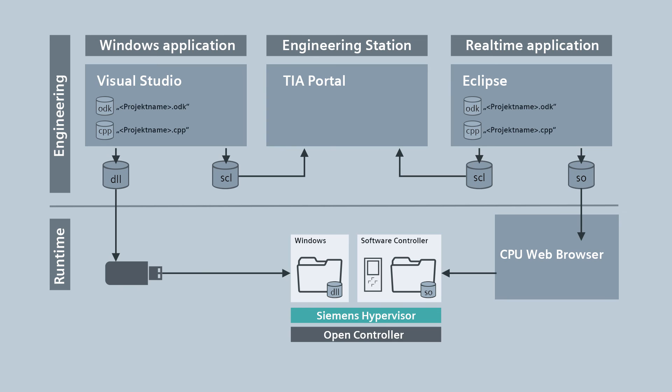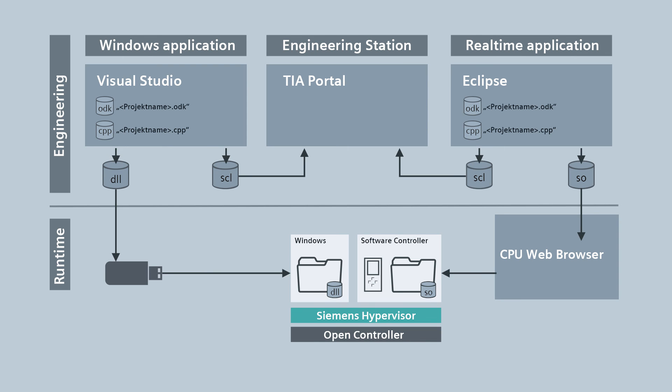You integrate the SCL files in the TIA portal as external sources and use them to generate function blocks for calling up the ODK application or for running the individual functions. You can connect these function blocks at will, integrate them into your program, and finally load the finished program into the OpenController.